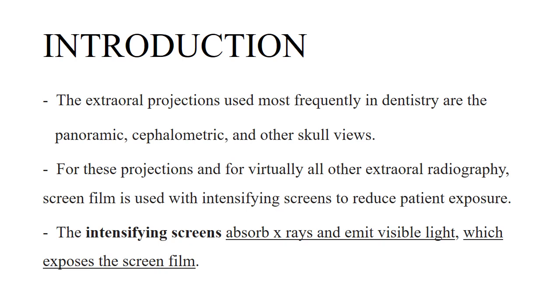Introduction. The extraoral projections used most frequently in dentistry are the panoramic, cephalometric, and other skull views. For these projections and for virtually all other extraoral radiography, screen film is used with intensifying screens to reduce patient exposure. The intensifying screens absorb X-rays and emit visible light, which exposes the screen film.